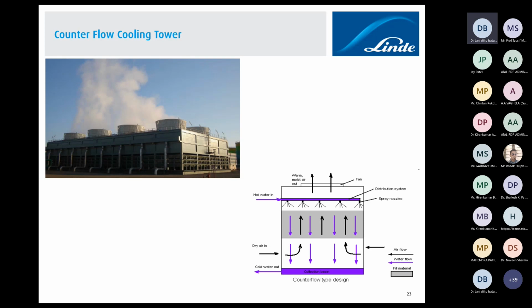I wanted to share that the performance of the cooling tower, as you mentioned earlier, greatly depends on the wet bulb temperature of the incoming air. Where ambient humidity is low, the cooling tower will give better performance. But when ambient humidity increases, the performance of the cooling tower drops drastically. That is one of the reasons why natural draft cooling towers suffer from environmental impacts. Correct.